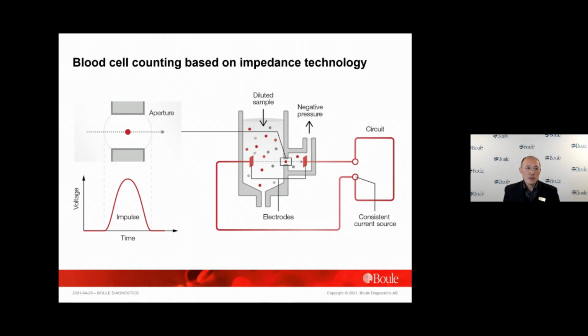M32 is a 3-part hematology analyzer built on a proven technology, impedance measurement. In principle, a particle passes through an aperture with a constant current loading, and the size can be measured by the voltage change when the particle passes the aperture. And to achieve high precision measurement, the system should let the particles move through the aperture in an even flow. So the laminar flow through the aperture will ensure there is no artifact, for example, coincidence events.